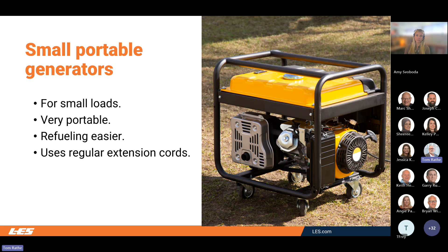So what do you really need to back up with your generator? Only you can determine that. You're going to have to determine your critical load, what that loss is going to cost you. Quite often, not everything in a facility is backed up with a generator. However, sometimes it's easier just to put everything on the generator and size your transfer switch accordingly. Again, your generator vendor, electrical engineer, or electrical contractor can all help you with cost options to do some or all of that.